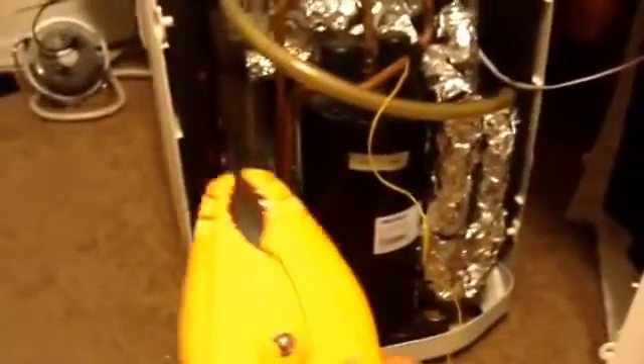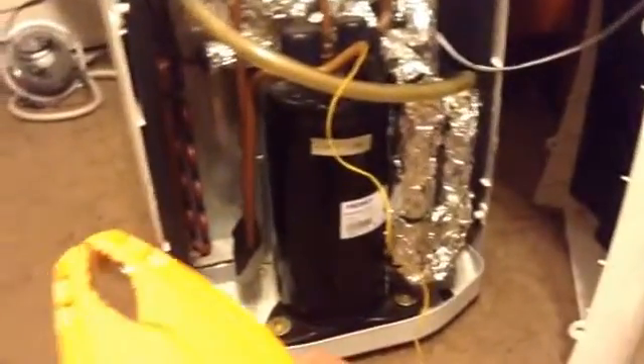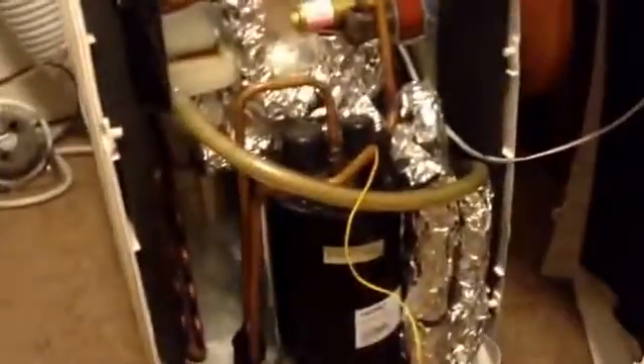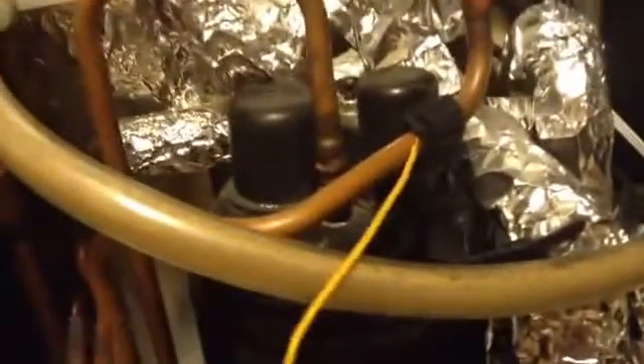It also has an accessory plug here for a Type-K plug for a temperature probe. It's actually a really narrow bead-type thermocouple, and it has a Velcro strap to attach it to smaller pipes. I also have a temperature clamp. This only goes down to 3/8-inch lines, which is average liquid line size on most residential air conditioners and heat pumps, and it's typically the smallest size line that you have to clamp. But if you're working on something small like my Soleus window heat pump — a 12,000 BTU heat pump that has 5/16-inch and quarter-inch lines — you're going to want to use the Velcro strap to secure it onto the pipe.